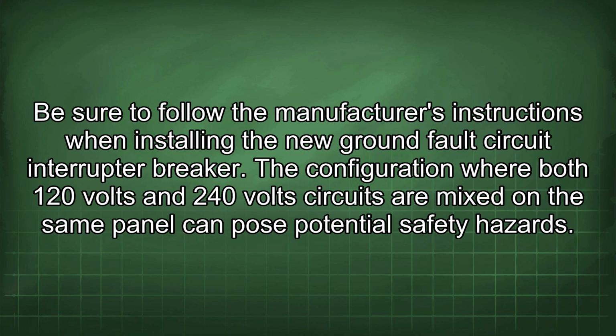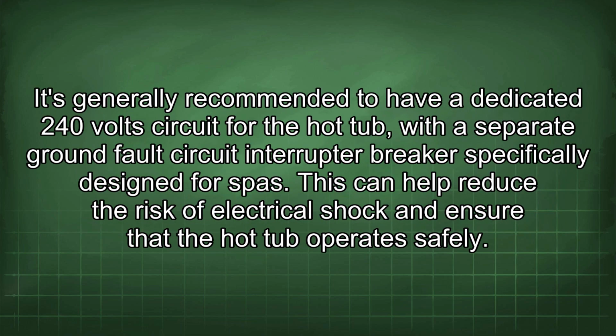The configuration where both 120 volt and 240 volt circuits are mixed on the same panel can pose potential safety hazards. It's generally recommended to have a dedicated 240 volt circuit for the hot tub, with a separate ground fault circuit interrupter breaker specifically designed for spas. This can help reduce the risk of electrical shock and ensure that the hot tub operates safely.